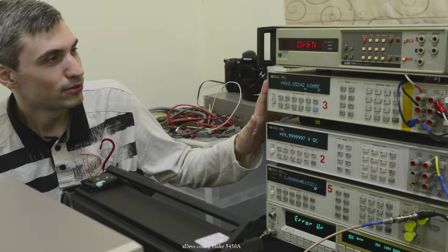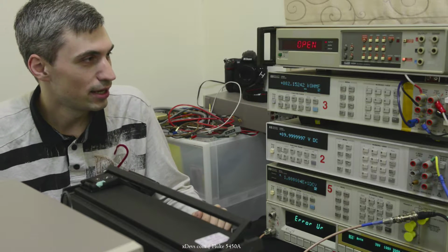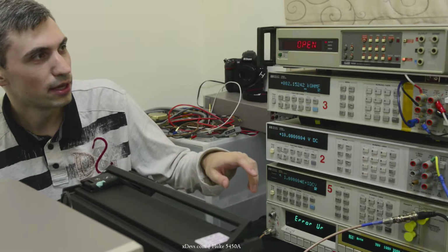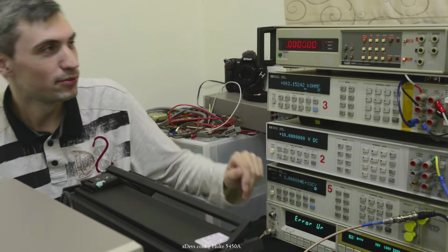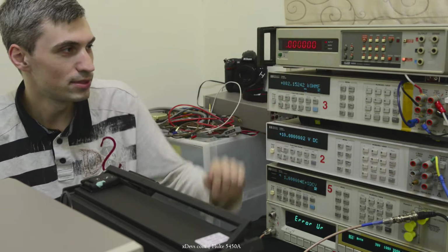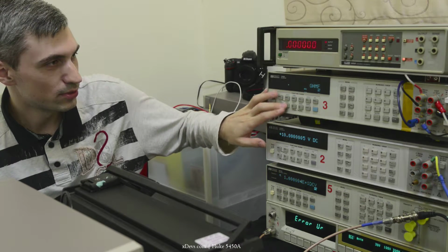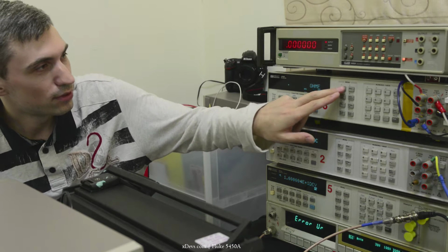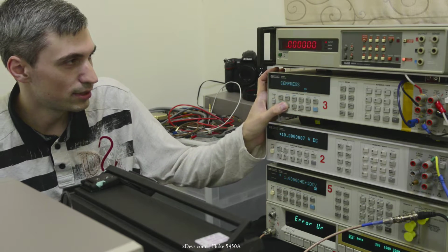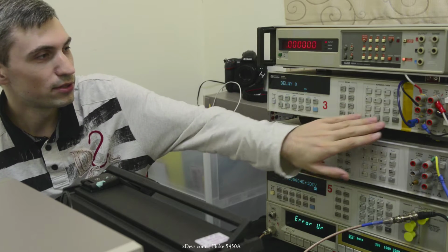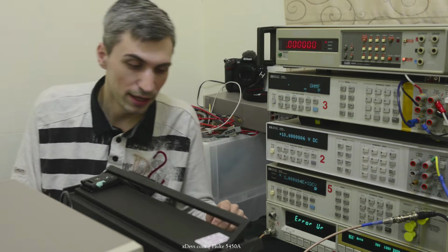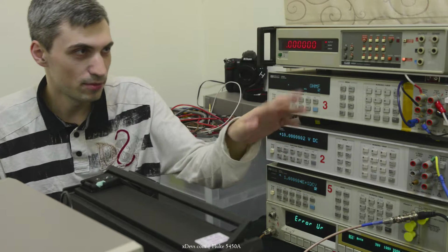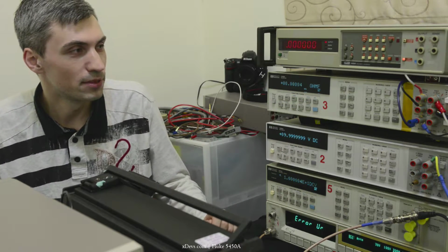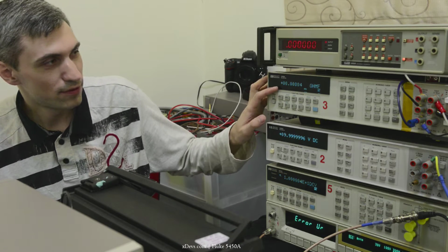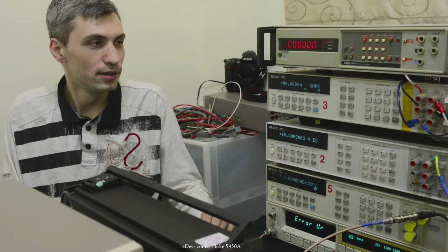So I just ran the auto calibration of the 3458A. What we can do is enable short, which should read like 000 ohms. For sake of this video I'll disable the delay, but for best accuracy you should always have a delay of 3 to 4 seconds due to cable effect and offset compensation. This is a 4-wire measurement, and I can zoom the camera in to make it closer.